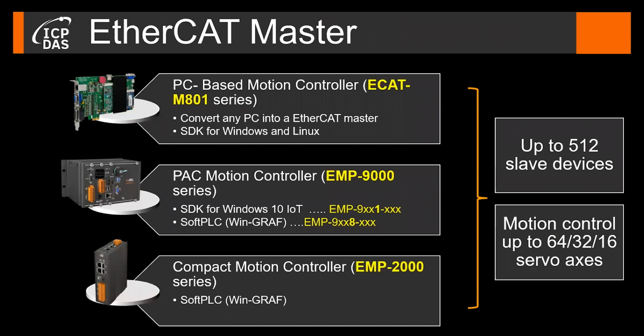ICP has three types of EtherCAT master in its portfolio. The EtherCAT master has an integrated, real-time, high-performance motion engine that can synchronously control multiple servo axes. The EtherCAT master types are the PC-based motion controller ECAT M801 series, the programmable automation controller EMP9000, and the EMP2000 series, a palm-sized, very compact motion controller. All masters are deterministic, fast, precise, and support a cycle time of up to 0.5 milliseconds. All EtherCAT operation modes are supported, such as DC, free run, and sync mode.